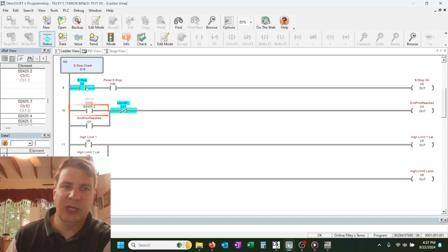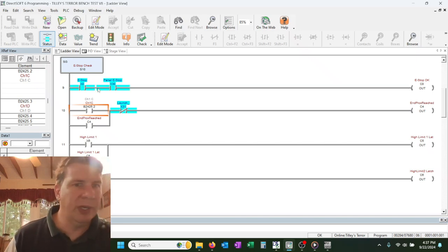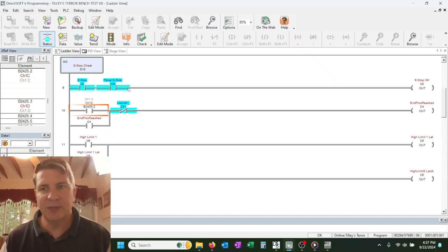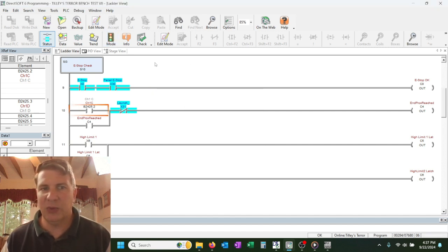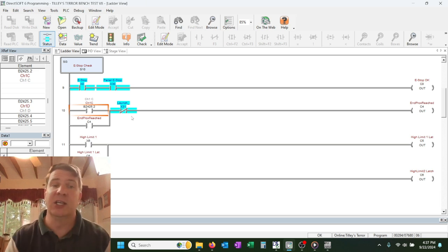We're going to be looking at our 2 e-stops, and here's our second one on the panel. Put that on. And at this point, our e-stop out would be okay, but I bet I'm in program mode. Yep, so that's not going to work right now. We're then going to be looking at our proximity sensors, and if any of these proximity sensors are high, it's going to latch those on because we're going to be going past them very fast, and they may not trigger automatically, so once you see a pulse, latch that thing on until something else breaks that.